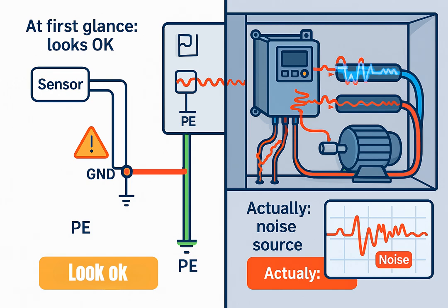Let's start with the most common mistake. On the drawing, you have an analog sensor. The positive signal, signal plus, is wired to the PLC analog input, AI plus. The sensor ground / 0 volts is wired straight to the PE bar in the cabinet. At first glance, this looks by the book. All green-yellow ground wires go to one PE bar. The cabinet looks neat and tidy. Everything goes to a single point. But this is actually a trap.